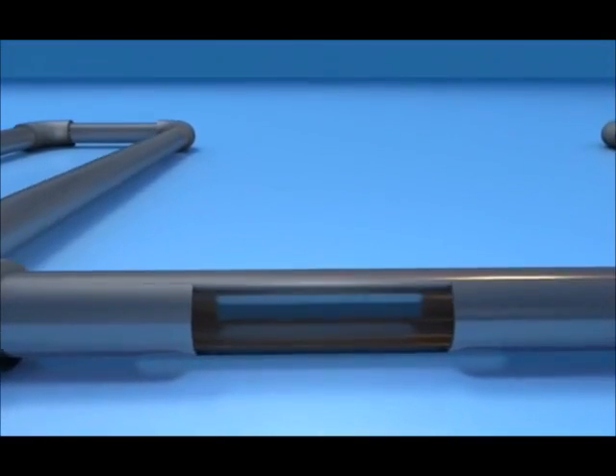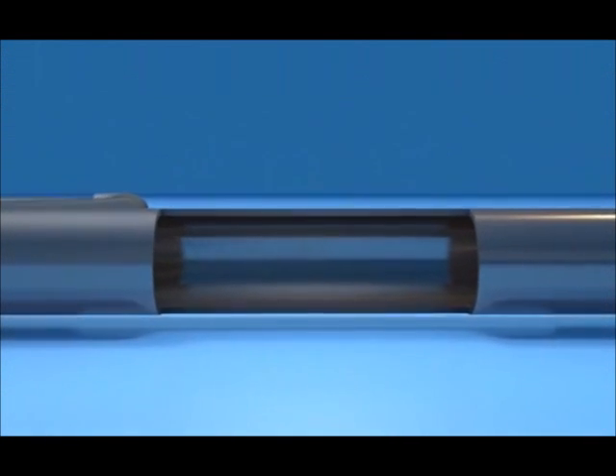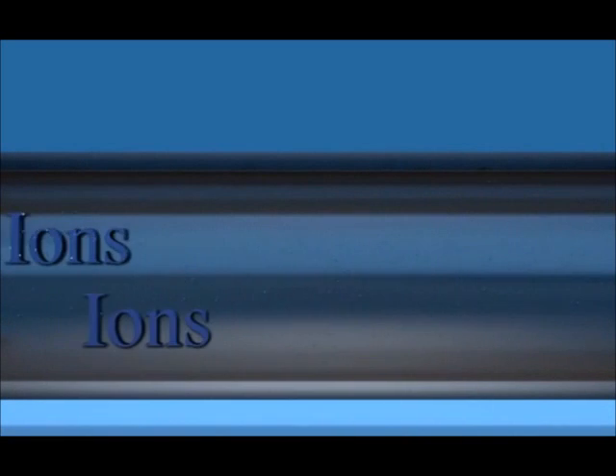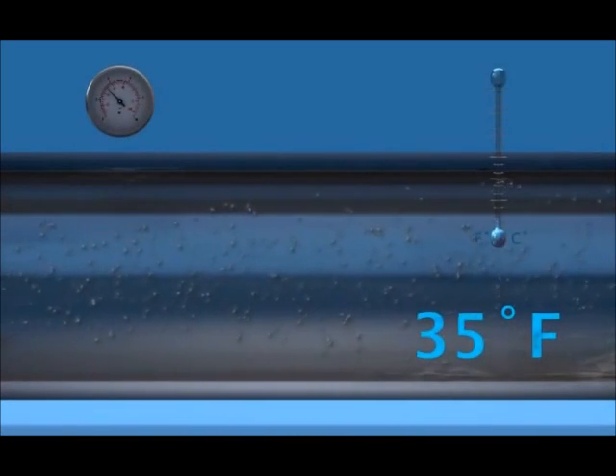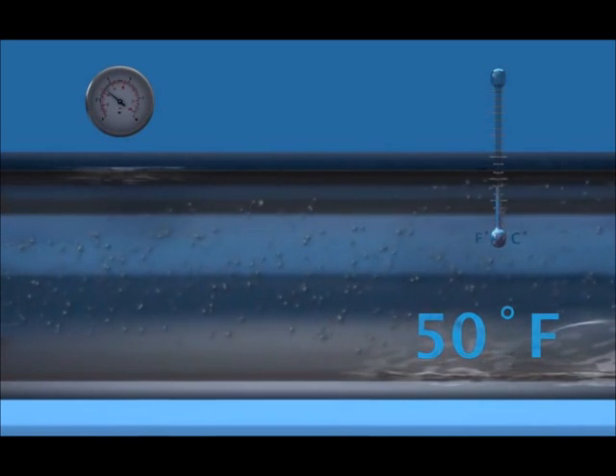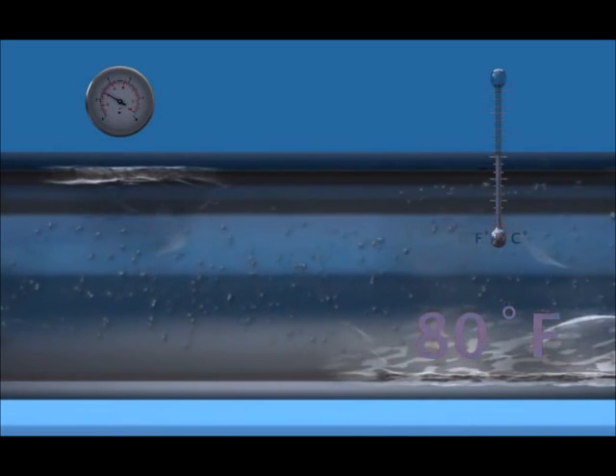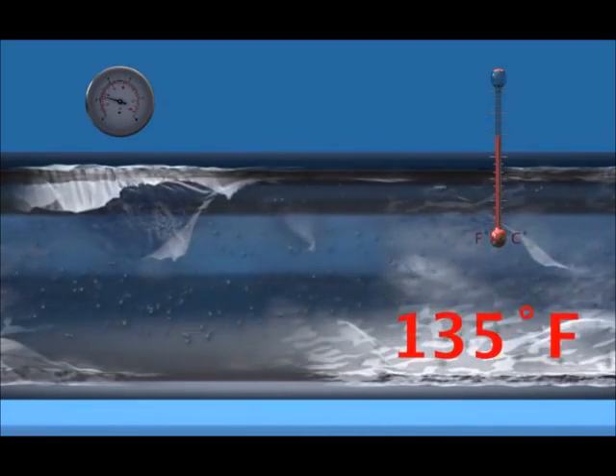A liquefied solution inside a piping system may contain minerals such as calcium carbonate dissolved in the form of ions. When temperature increases or a pressure drop occurs, the solution will become supersaturated. This will cause the ions to precipitate out of solution and adhere to the piping and equipment surfaces in the form of scale.